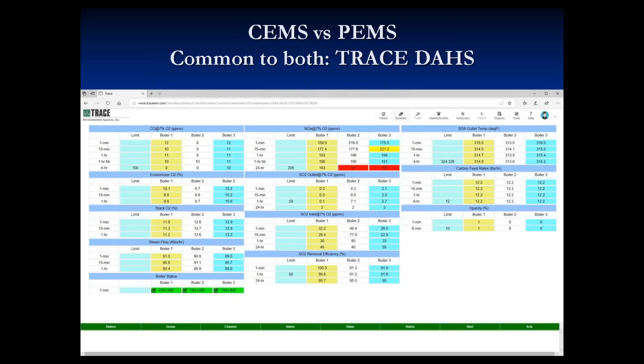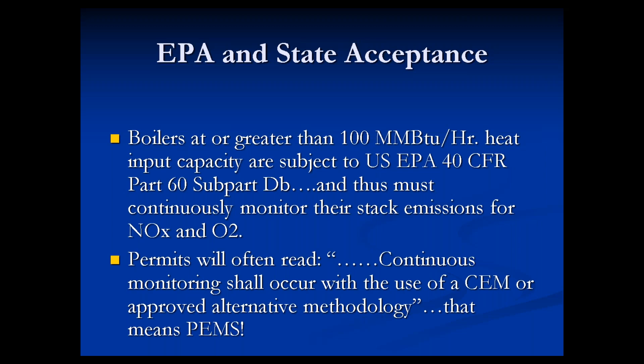So getting into the regulatory aspect of this, as many of you know, taking a boiler, for instance, those at or greater than 100 million BTU per hour heat input capacity are subject to subpart Db of 40 CFR Part 60, and therefore need to continuously monitor for NOx and O2. You'll see some regulatory agencies also requiring CO. But in many instances, when a permit is issued for such a source, it will read something to the effect that the monitoring shall occur with the use of a CEM or an approved alternative methodology. And when you see that, that means PEMS.